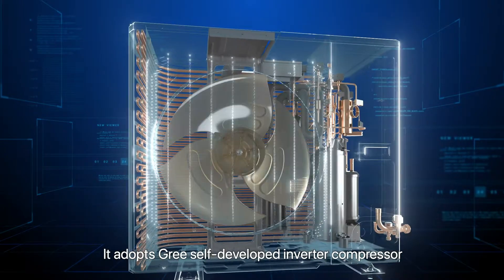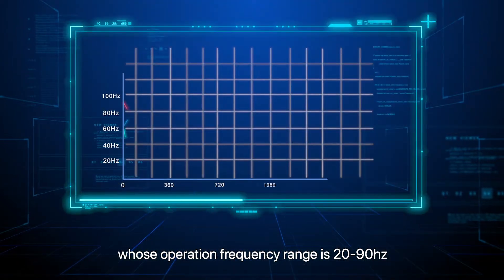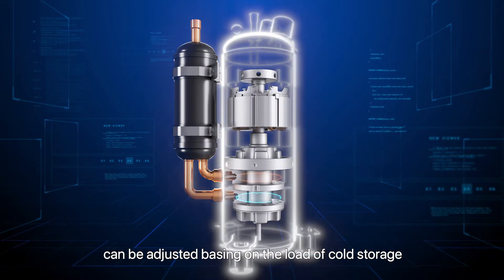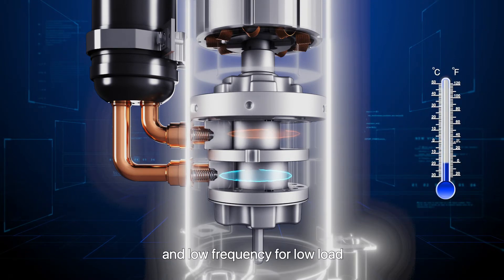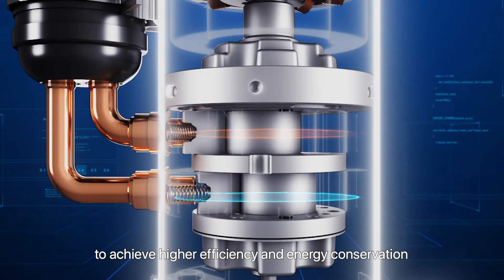It adopts Gree self-developed inverter compressor whose operation frequency range is 20 to 90 Hz. The operation frequency of the compressor can be adjusted based on the load of cold storage — high frequency for high load to decrease the temperature rapidly, and low frequency for low load to achieve higher efficiency and energy conservation.